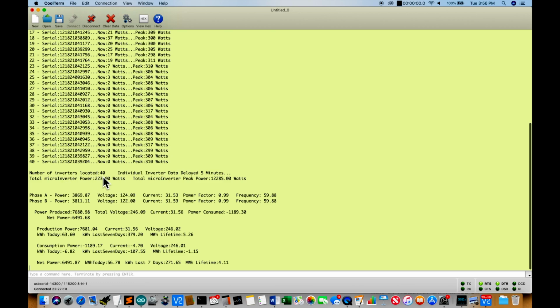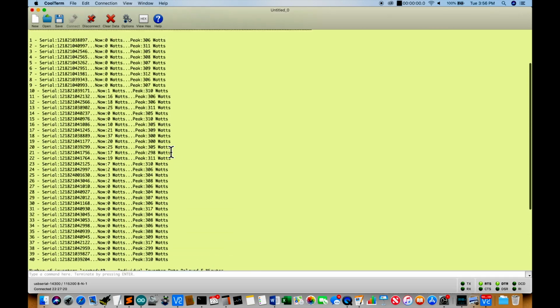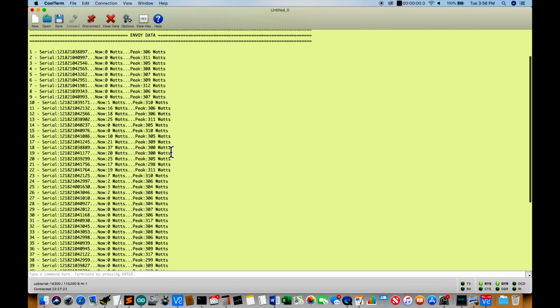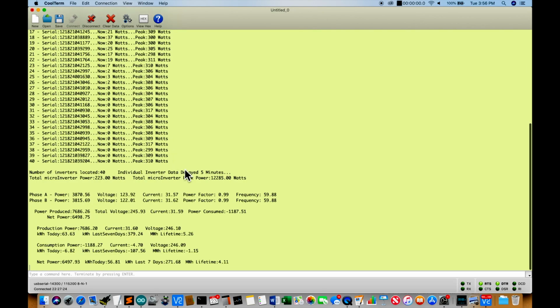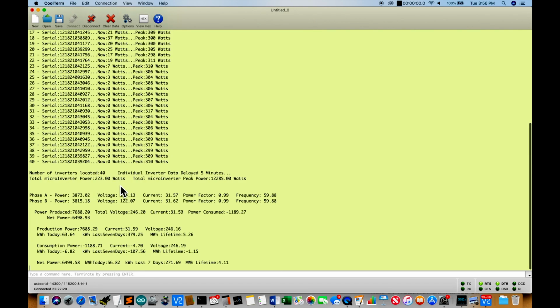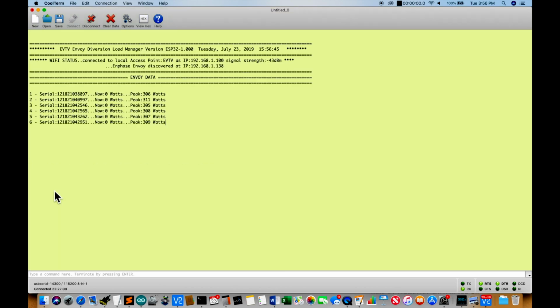This is telling me that we located 40 inverters and reminding me the individual inverter data is delayed 5 minutes. That might be 5 minutes depending on when it was last done, but it updates every 5 minutes. Total microinverter power at the moment is 223 watts. Total microinverter peak power has been 12,285.